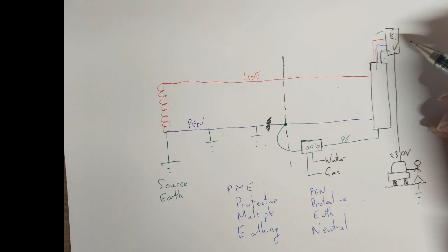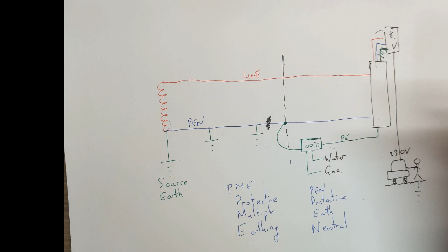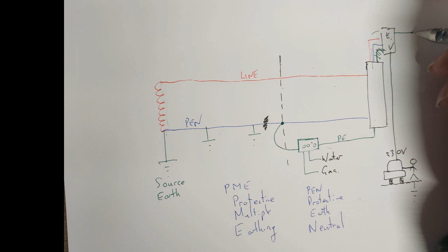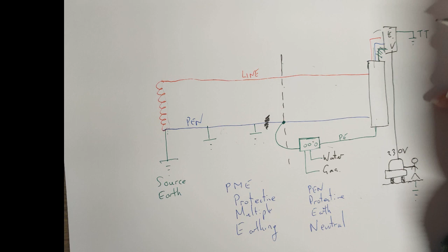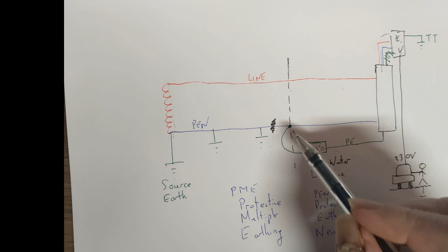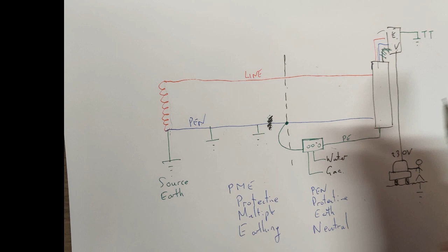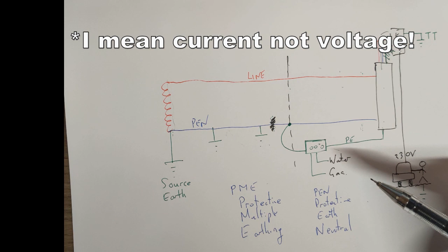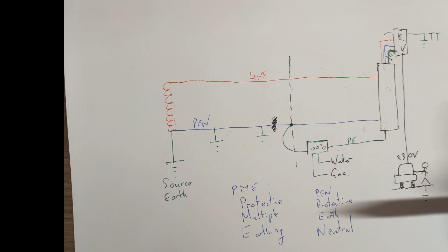In 722, there should be no way of any earthing being used in a TNCS system that can go back to the transformer. It has to have its own earthing arrangement, which is TT, or there must be something inside this that can detect when that happens. Now you might be saying, well, why didn't the RCD fire? Well, because there's no difference in the current on these two lines. In an earth fault, there'll be a difference between these two lines in the current, and that's what triggers your RCD. But there isn't in this case. The RCD is perfectly happy.